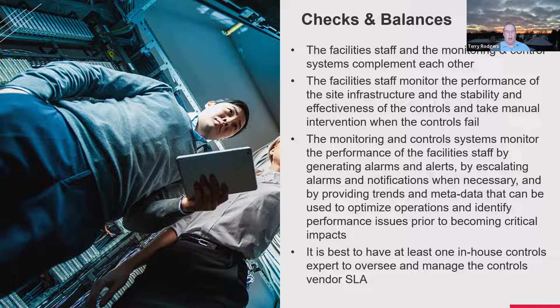monitoring and control systems. So at a very high level, a lot of people consider commissioning, unfortunately, after all this time, to be, we build it and we bring the commissioning agent in and he tests it. And that's not commissioning, that's what we call acceptance testing. Commissioning starts at the very beginning of a project in the programming phase. Per ASHRAE Guideline 0, the commissioning agent should actually be the one who facilitates an owner's requirements workshop and then captures that in a formal document called the owner's project requirements.